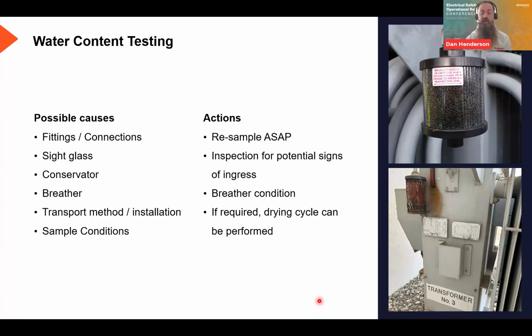And then finally, there's many other possible causes, but on the sample conditions, the most common thing that I'll see is you'll get a recommendation back saying water content. And often if you're using the same lab or tracking your results, which is really good to do, you build up that asset history. So if you haven't had any water ingress before, then suddenly on a sample report you've now got water ingress, there's been that fundamental change.